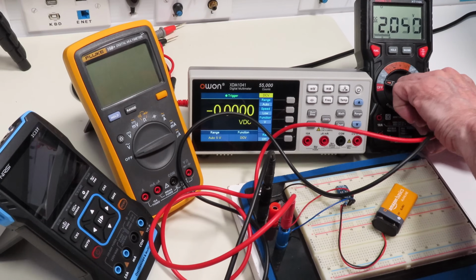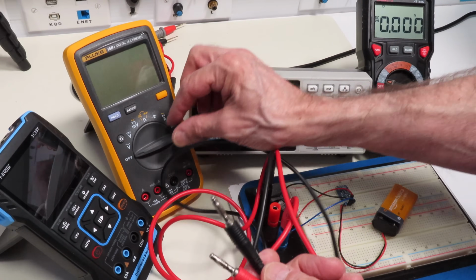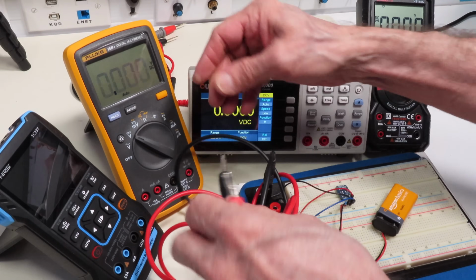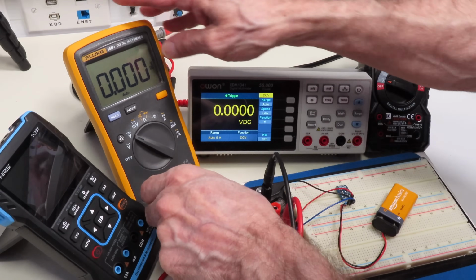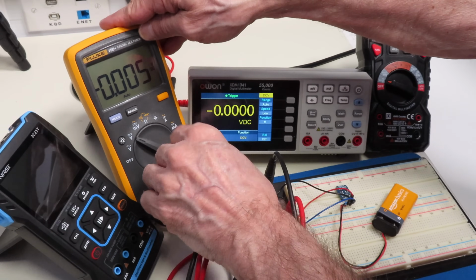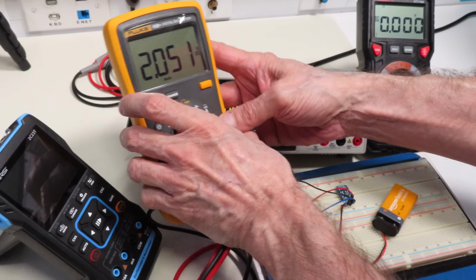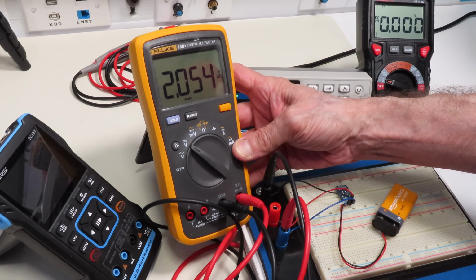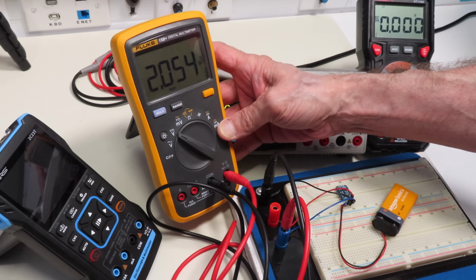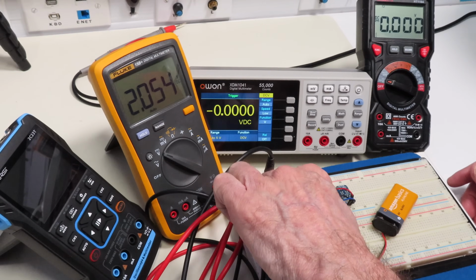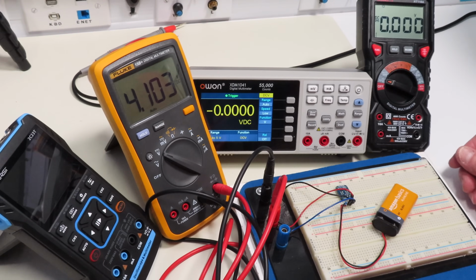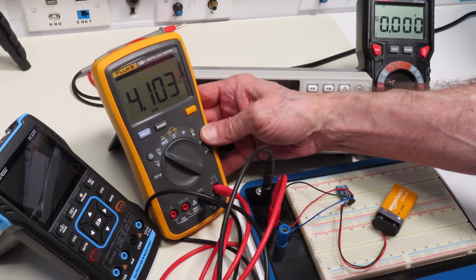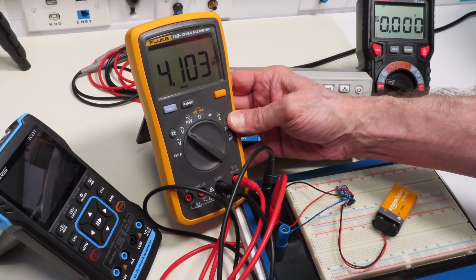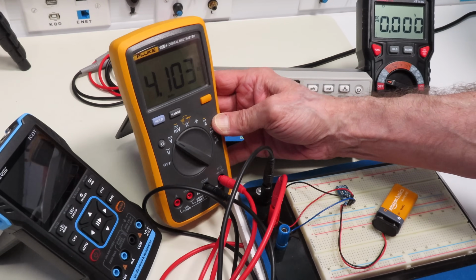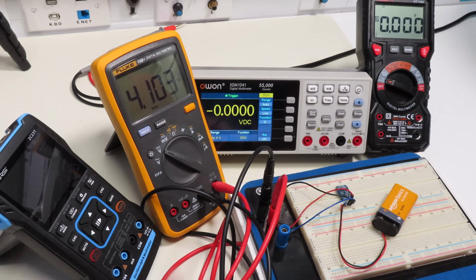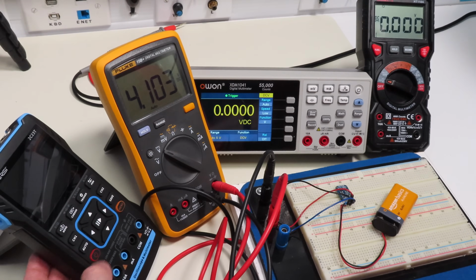Okay, let's go over to the Fluke. This, of course, is our most expensive meter. Right now we're feeding it 2.048, and it reads 2.054 - close, not exact, but pretty close. And the 4.096 is actually reading 4.103, so off by a little bit, not too much, but a bit. And remember, that is the most expensive meter I've got here.